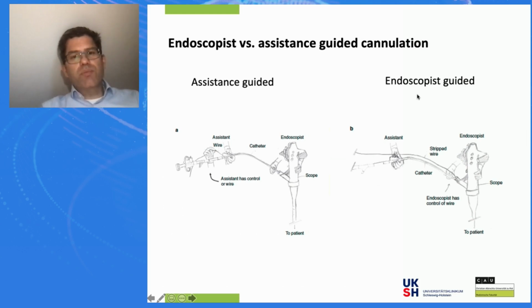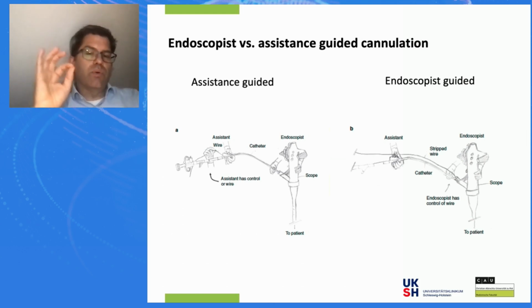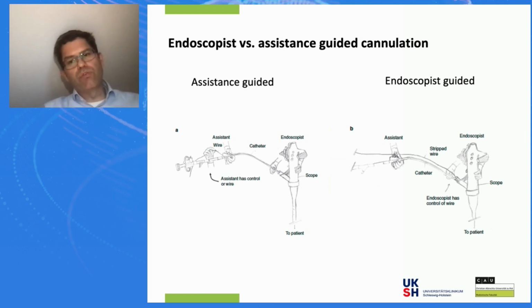With the endoscopist guided cannulation, you manipulate your instrument to the distal part of the endoscope, and then we already split the guide wire from the instrument, and then the endoscopist by himself can easily manipulate the catheter with the working channel, with the elevator, and in addition, we are able to maneuver and manipulate the guide wire on our own.